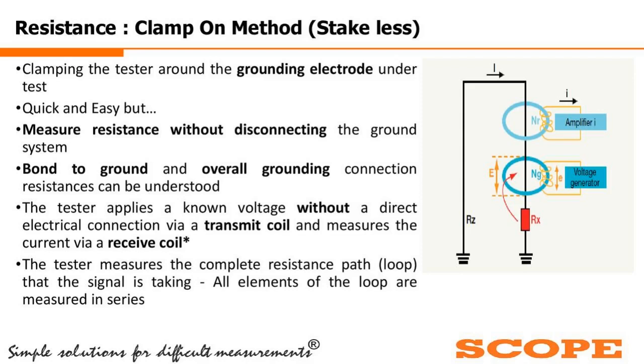Because here we are not measuring any specific point, we are going to get a loop, as we mentioned in the last point. The tester measures the complete resistance path, the loop that the signal is taking. All elements of the loop are measured in series. So when we are measuring the current, and from that we get back the resistance value, we are not getting the value of that individual earth pit. We are practically going to get the resistance of all elements in that current loop, whatever is there. When it comes to the one with injection, the tester will apply a known voltage without a direct electrical connection via a transmit coil, and it will measure the current via the receive coil.